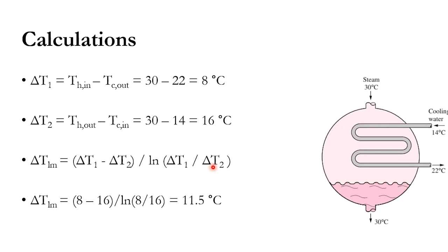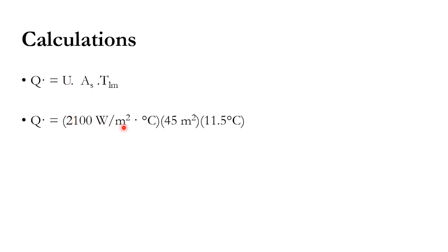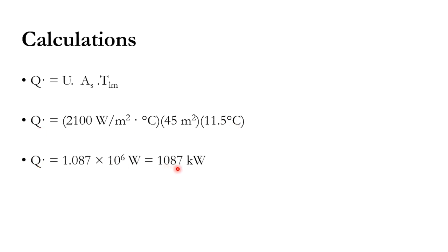The log mean temperature difference is 11.5°C. Using Q = U·A·ΔT_m, with U = 2100 W/m²°C, area = 45 m², and LMTD = 11.5°C, the overall heat transfer rate Q is calculated as 1087 kW.